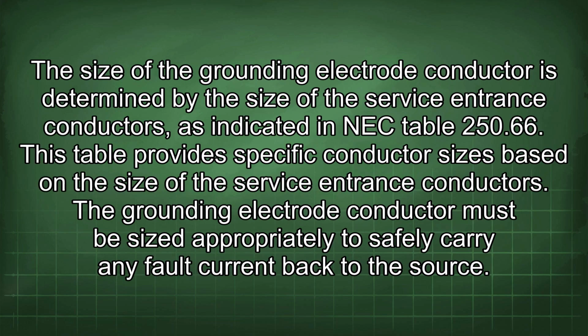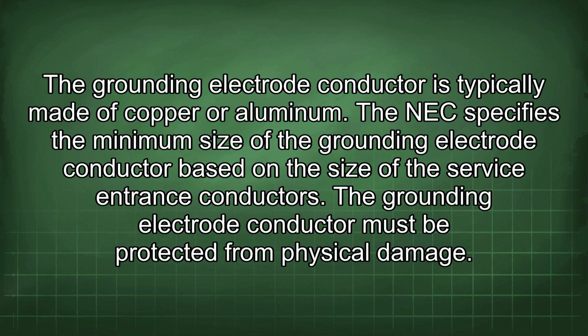The size of the grounding electrode conductor is determined by the size of the service entrance conductors as indicated in NEC Table 250.66. This table provides specific conductor sizes based on the size of the service entrance conductors. The grounding electrode conductor must be sized appropriately to safely carry any fault current back to the source. The grounding electrode conductor is typically made of copper or aluminum. The NEC specifies the minimum size of the grounding electrode conductor based on the size of the service entrance conductors.